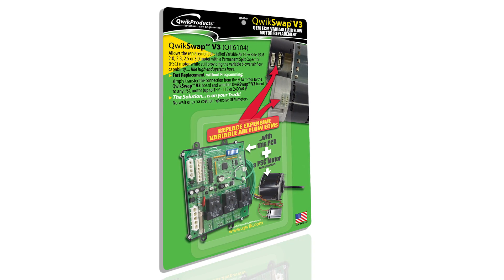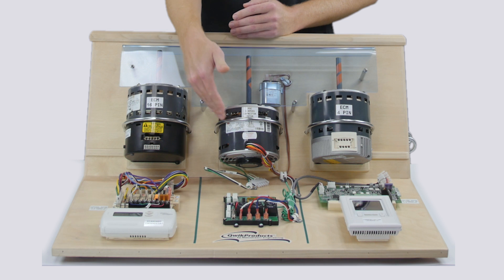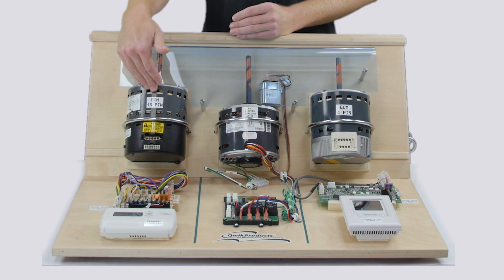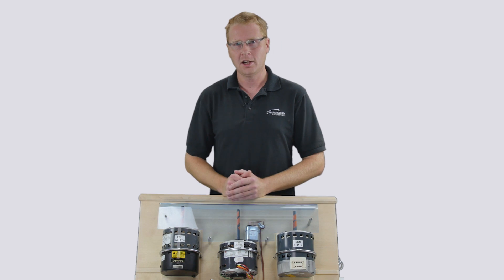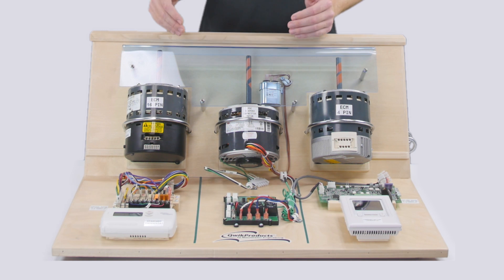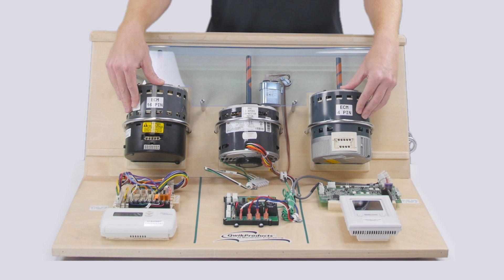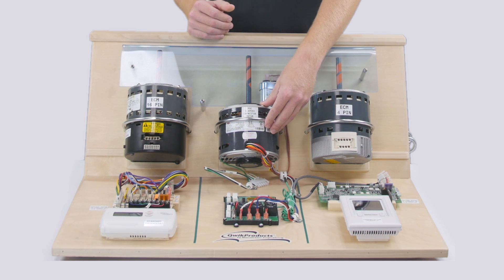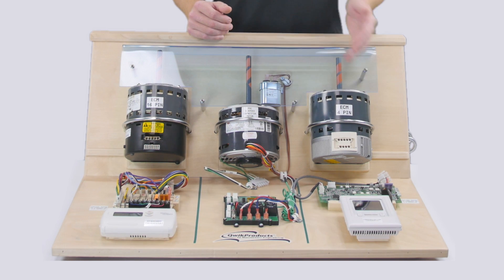The QwikSwap V3 is the solution to that problem. It controls a three-speed PSC motor and can be used as a direct replacement to the 16-pin ECM or a four-pin ECM, and it's economical enough to carry on your truck. What we have here is a demonstration fixture with a 16-pin ECM, a four-pin ECM, and a three-speed PSC motor with a QwikSwap V3 that can be used to replace either of these two motors.